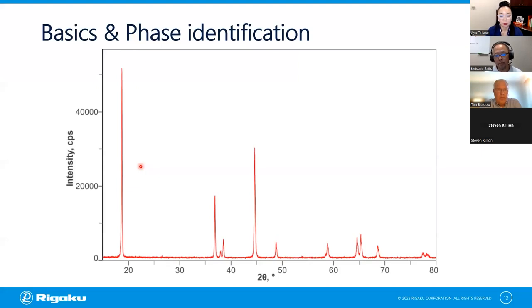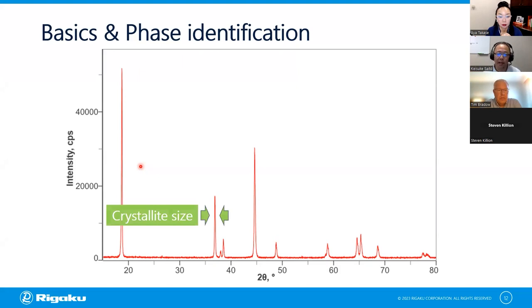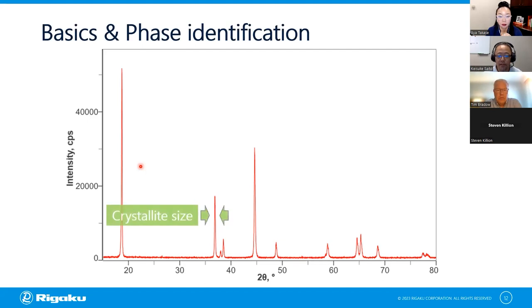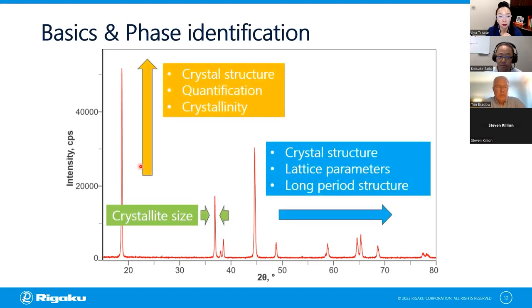In a specific configuration, we have the X-ray source on the left-hand side. The X-ray generated is collimated and monochromated by the optics. Your sample is placed in the sample holder on the sample stage, and the diffracted beam is recorded by the detector on the right-hand side. We measure the diffracted beam intensity against scattering angle 2-theta. From the peak width you can analyze crystallite size; from the horizontal position you get crystal structure and lattice parameters. For polymers, this includes the long-period structure.